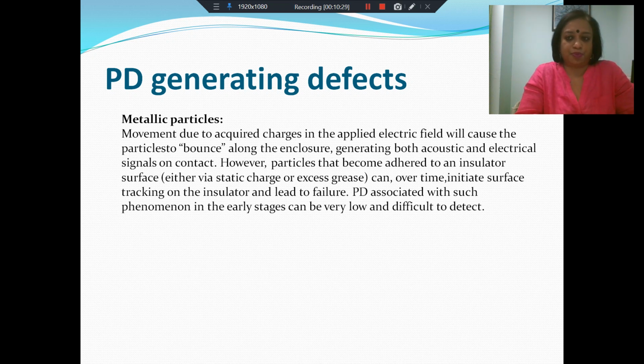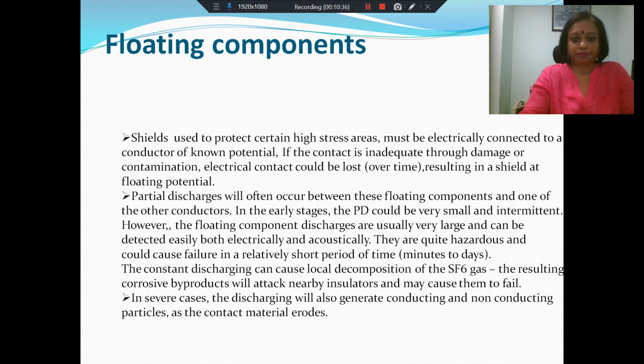However, the movement due to particles which cause PD on the enclosure surface can be detected with better ease. Then we have floating components. As I said, there are many components inside the GIS enclosure. For example, one of them is shields.